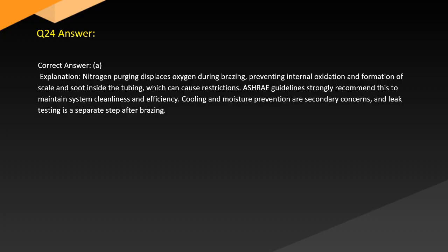Answer. Correct answer: A. Explanation. Nitrogen purging displaces oxygen during brazing, preventing internal oxidation and formation of scale and soot inside the tubing, which can cause restrictions. The ASHRAE guidelines strongly recommend this to maintain system cleanliness and efficiency. Cooling and moisture prevention are secondary concerns, and leak testing is a separate step after brazing.